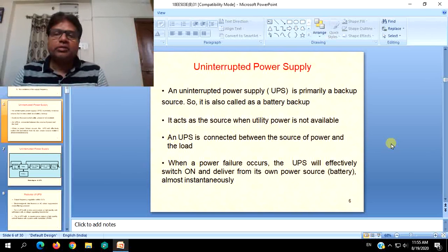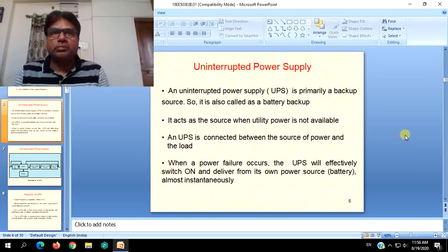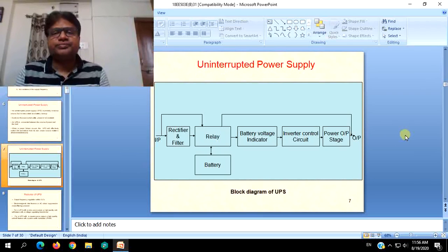This particular delay time varies from UPS to UPS, and also with the quality of manufacture and design with which these UPS are designed. The gap of the delay time, or response time, should be as small as possible. In most cases, it should be less than or equal to a quarter of a cycle. We will be discussing it later.